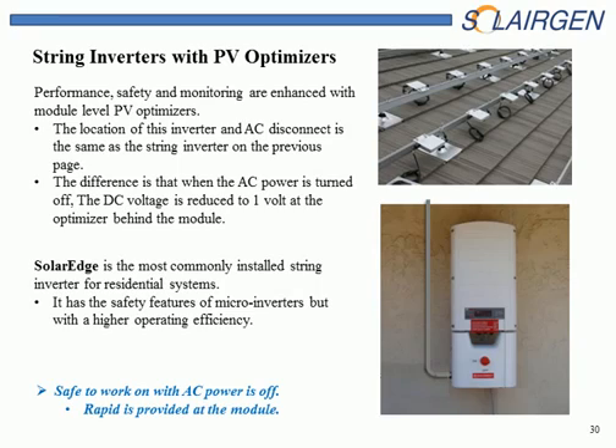I've mentioned the name SolarEdge a few times. They are the only inverter that is matched to their PV optimizers. They're not the only company that manufactures PV optimizers. They're getting more and more popular and more common. And here they have the optimizers mounted behind where the modules are actually going to go in place. So if you see the SolarEdge, just disconnecting the AC will turn this off automatically. So look for the SolarEdge. And as we move into the industry as it develops, you'll see more of these optimizers competing with these guys. And you should see that indicated on the DC disconnect that it does have an optimized rapid shutdown system.